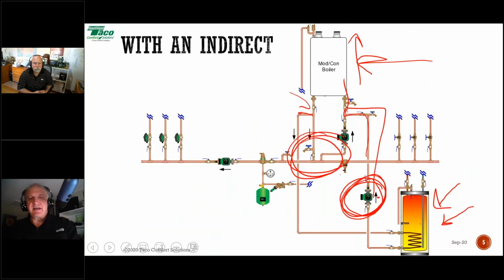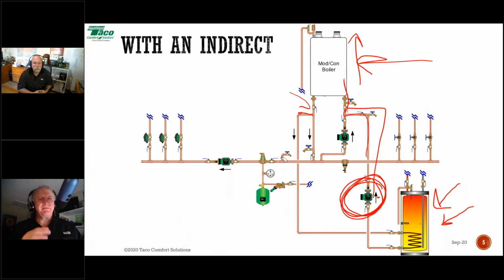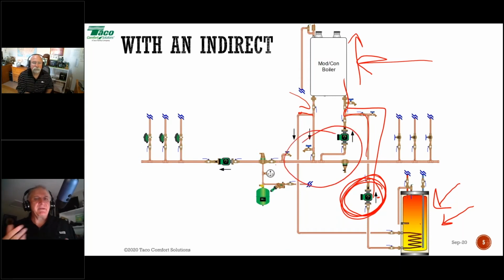Well, I look at this type of piping, building your own header. It's going to depend on how many zones you have, the size of the smallest zone, as well as the lowest firing rate of the boiler. If you've got a system where maybe it's a boiler replacement and you've got an old Venturi system or an old two-pipe system where it's one, maybe two zones, all right, and you've got a turn down ratio of 8 to 1 or 7 to 1 or 6 to 1 or whatever it might be. As long as you don't have too many zones, that piping arrangement's just fine, just fine.